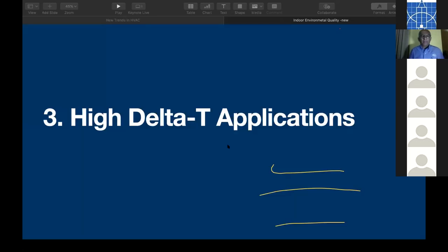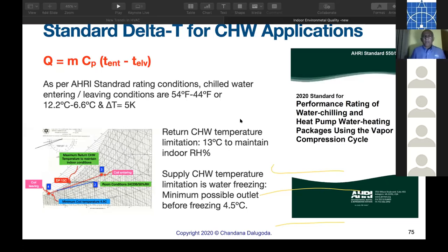Then high delta T. I hope I'm not going through too quickly. High delta T applications. I don't know, very few applications here, but we know high delta T is a benefit, of course. Now, before that, standard delta T, what is standard delta T? It is from the AHRI standard, not as we want. Chillers are tested to the AHRI 550/590 standard. The temperature difference of the chiller inlet and outlet is taken as 54 Fahrenheit and 44 Fahrenheit. When you convert, it is 12.2 and 6.6. We take it as 12 to 7 with a 5K delta T.